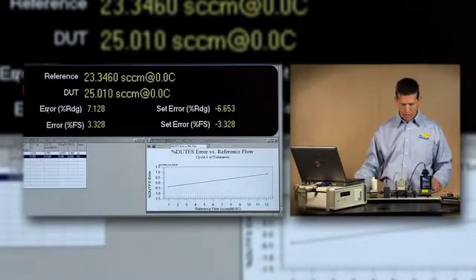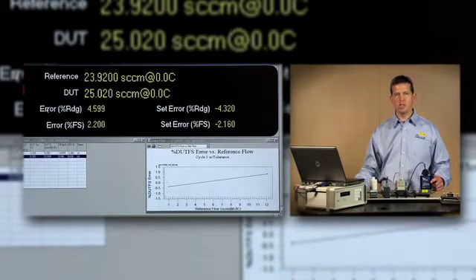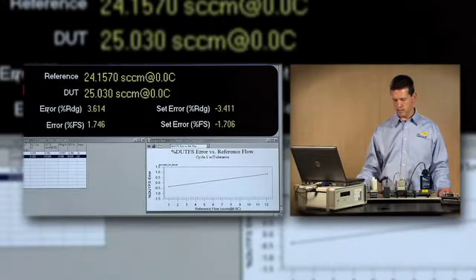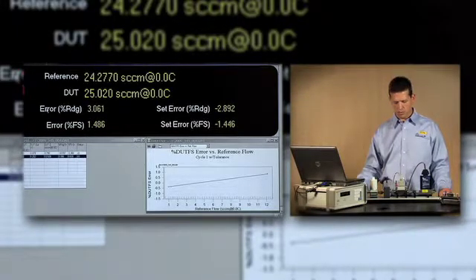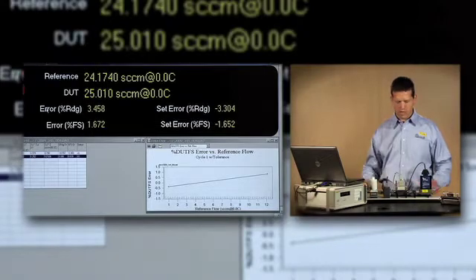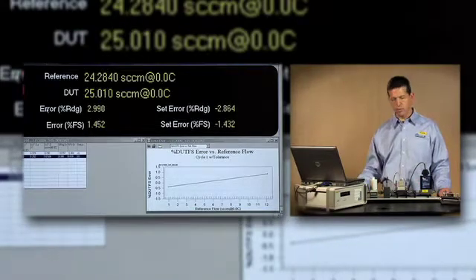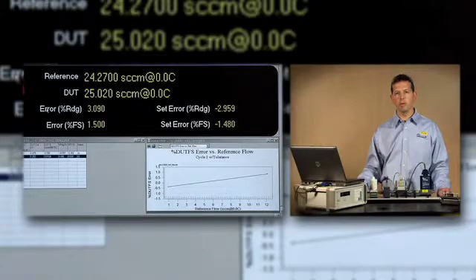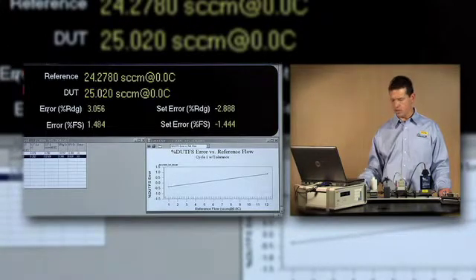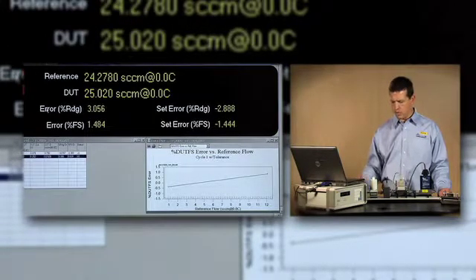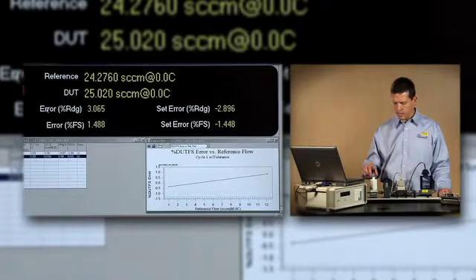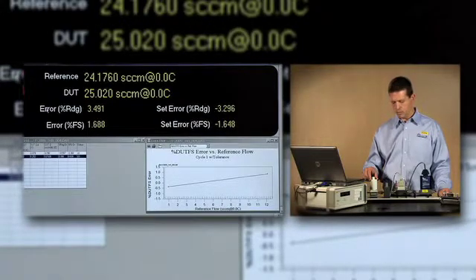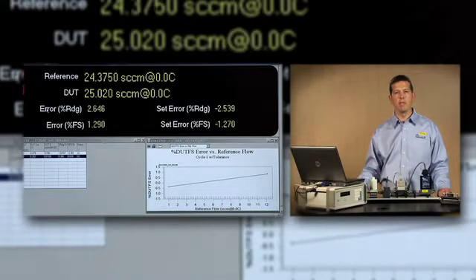The Molbloc and the MFC are both sitting on a mounting platform called a Molstick. The Molstick, in addition to providing convenient connections and mounting for your Molbloc and device under test, also includes all of the components needed to provide a stable pressure and clean supply gas. We have a filter on this Molstick, a specialized pressure regulator used for low flow, and a shutoff valve.